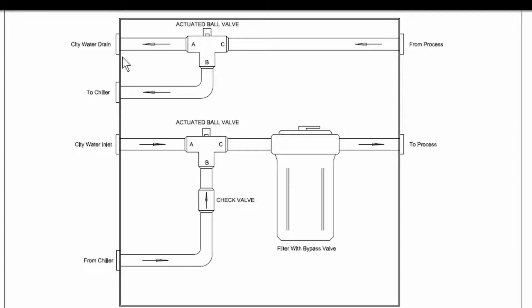All right. So what you have here is the wall-mounted city water panel that Legacy Chillers manufactures. We have these panels available with both filtered and non-filtered. So we're looking at a filtered version of it here. On the left-hand side, we have 4 connections. So we have our city water inlet. Very important, if you buy a panel without a filter, you need to make sure that you have an external filter on here. Because if there's any debris or contaminants that make their way in from the city water, you want to make sure that there's a place to stop it before it goes into your process. Some processes like CTs and MRIs do not deal with contaminants very well.